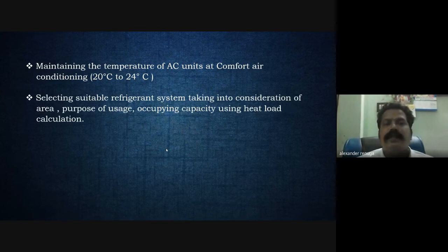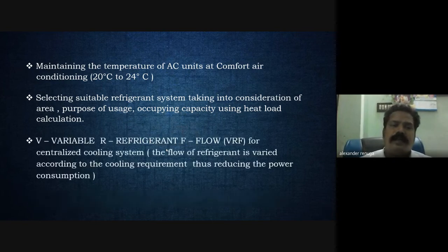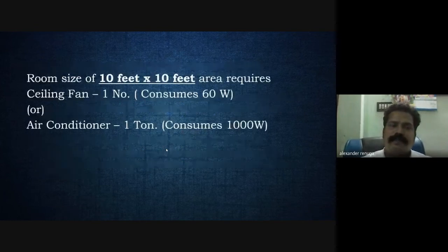Select suitable refrigerant systems, taking into consideration the area, purpose of usage and occupying capacity, using heat load calculation. Then the VRF system, that is variable refrigerant flow, for a centralized cooling system. For a centralized AC system, nowadays we prefer only this VRF system. The flow of refrigerant is varied according to the cooling requirement, thus reducing the power consumption.